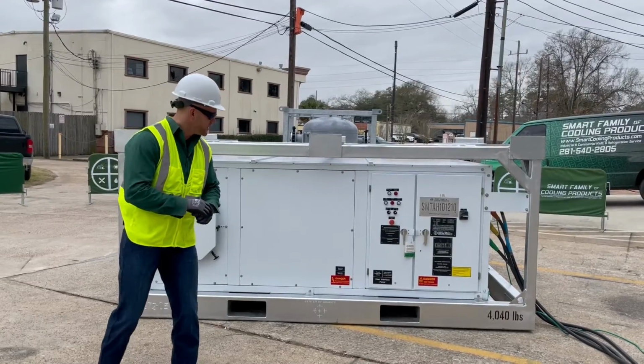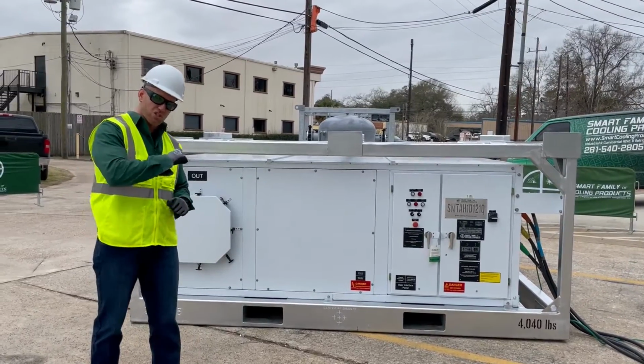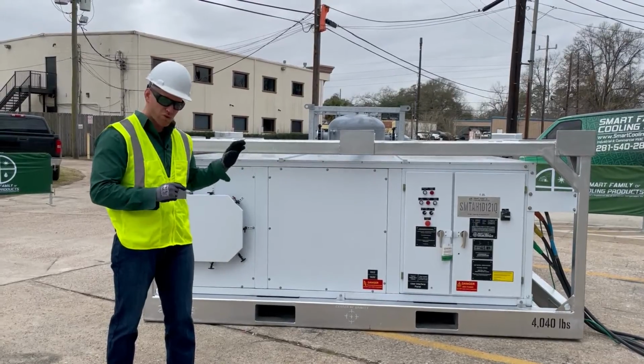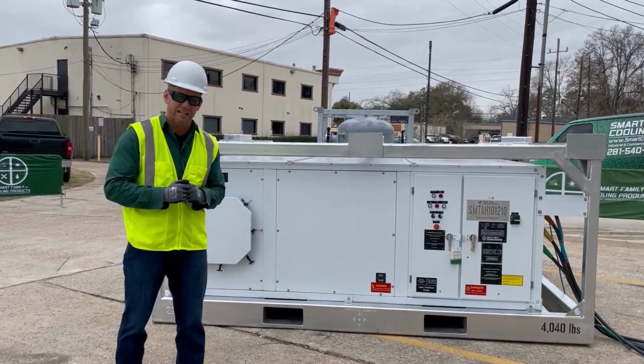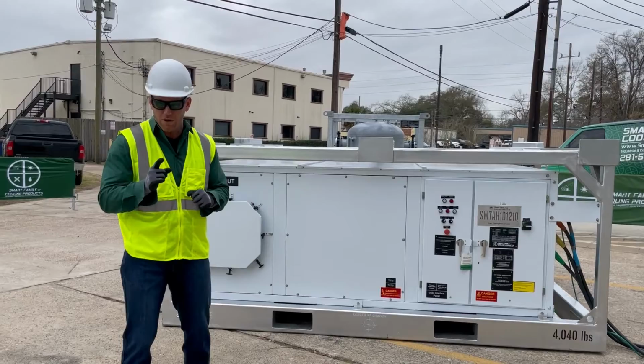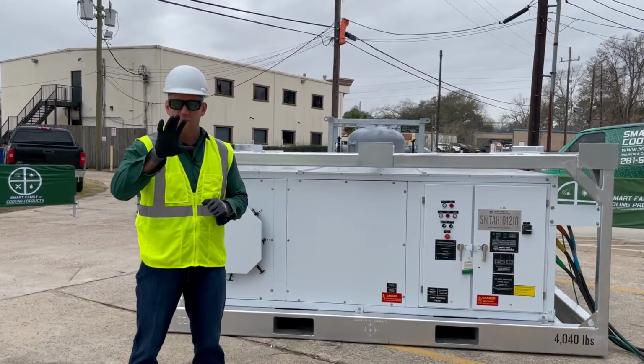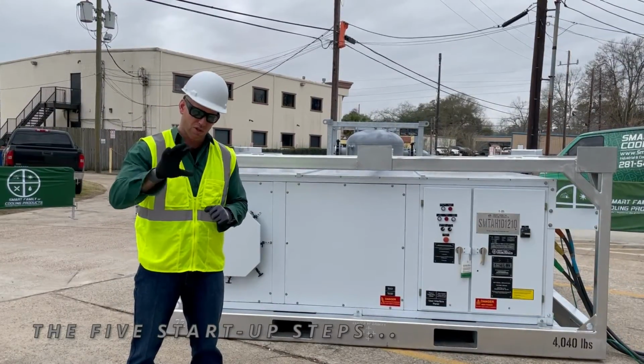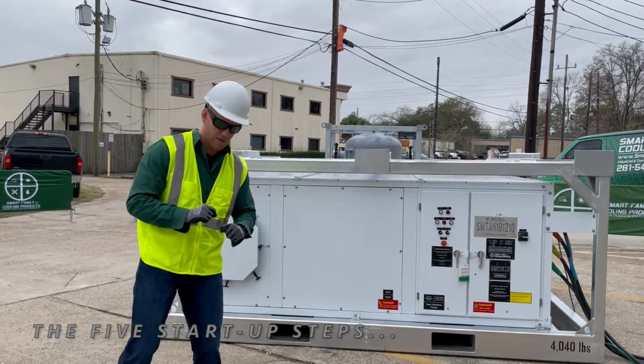Okay, great. Now that we've handled safety, let's go through the startup steps on starting up our 120-ton industrial high-static air handling unit. For most Smart Family gear, there's a 5-step process that we use when we're doing a startup on these machines. So I'm going to go through that with you now.